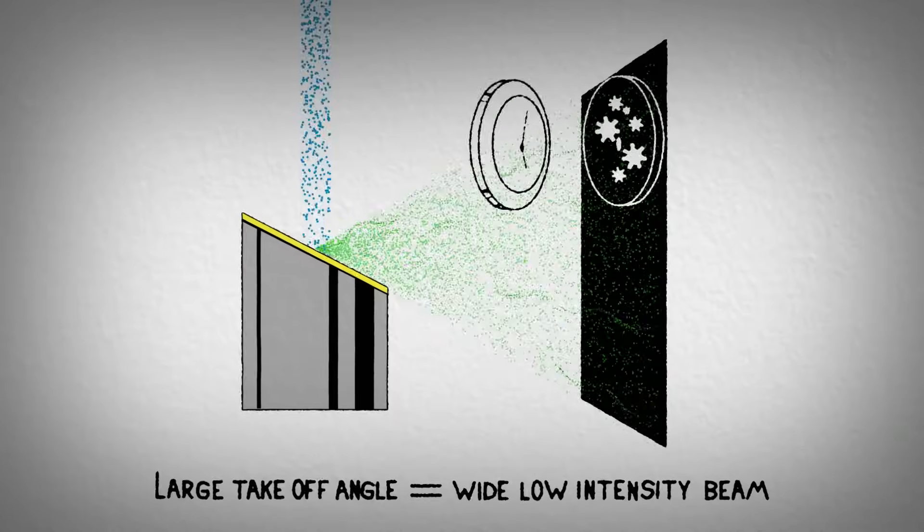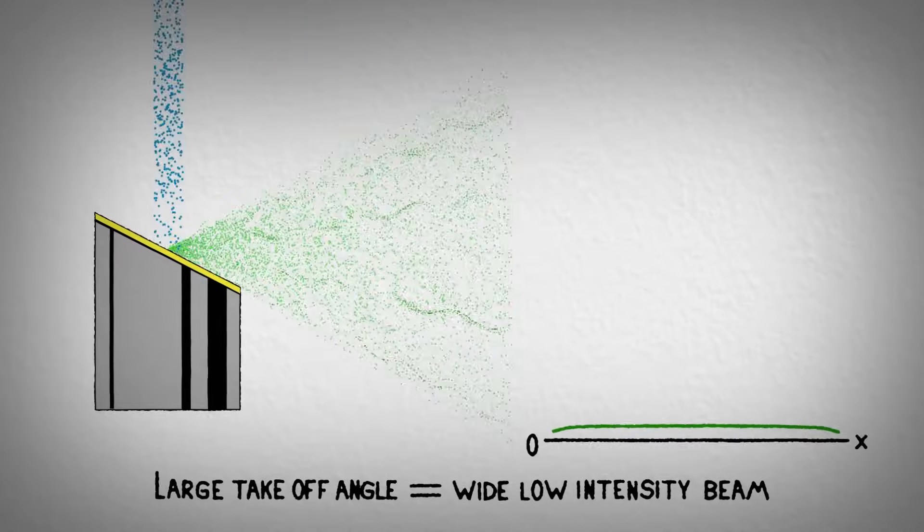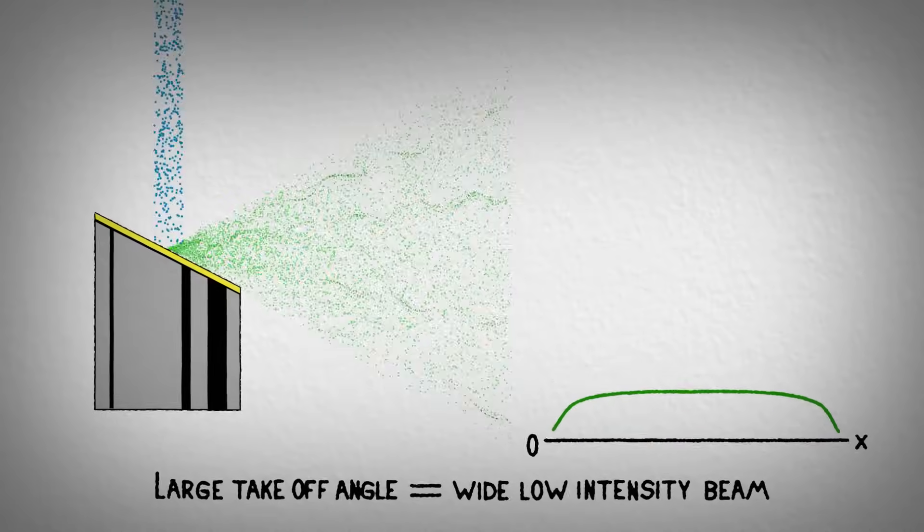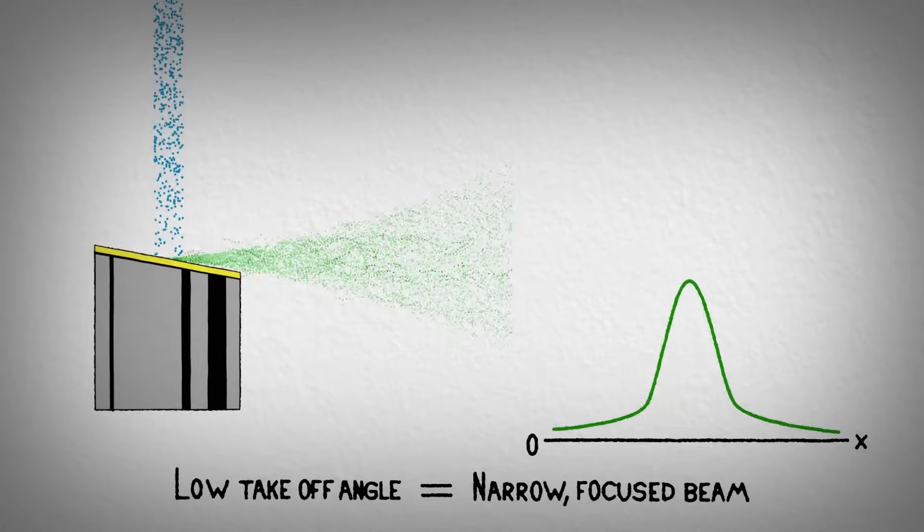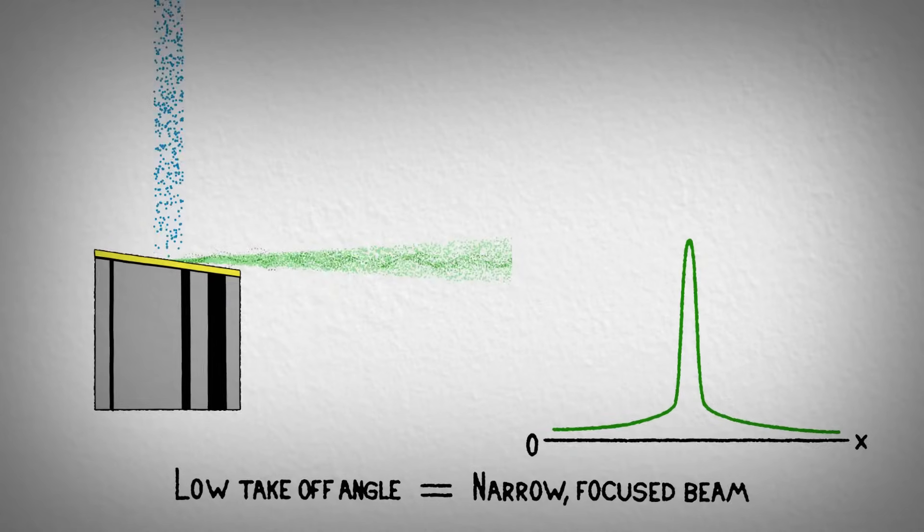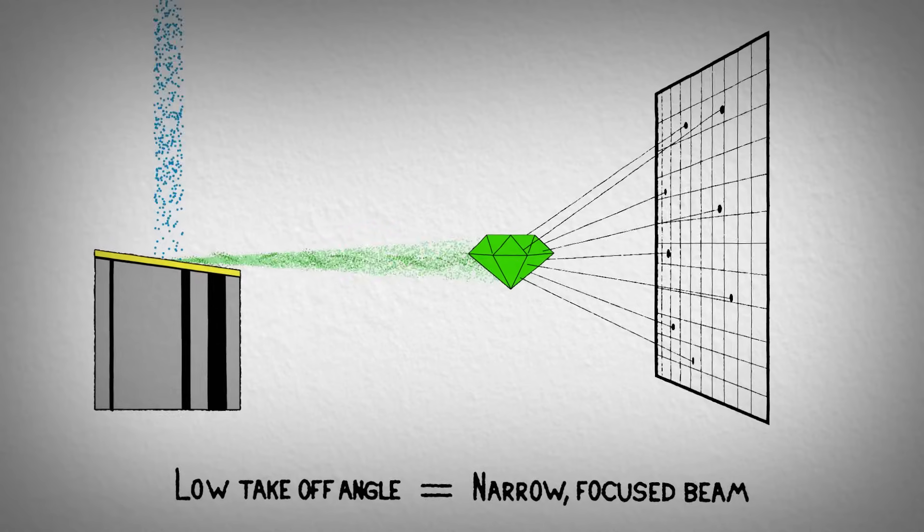Tubes designed for non-destructive testing and imaging applications typically have a high takeoff angle, providing a wider spreading and even dispersion of the X-ray flux. As the takeoff angle is lowered, the beam intensity and energy focus increases. Tubes with low takeoff angles are ideal for single-crystal diffraction experiments.